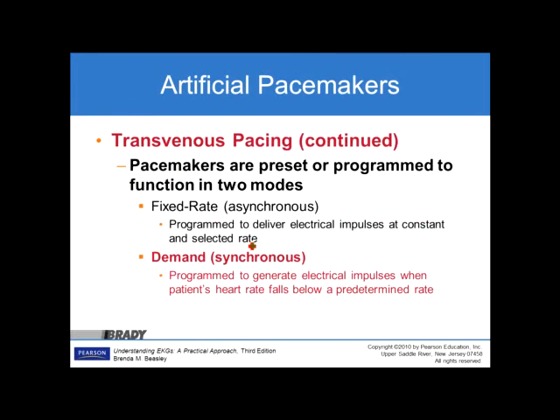Pacemakers are preset and programmed to function in two modes. Fixed rate, or asynchronous, is programmed to deliver electrical impulses at constant and selected rates. Demand, or synchronous, is programmed to generate electrical impulses when the patient's heart rate falls below a predetermined rate. So essentially these are demand and non-demand pacing modes.